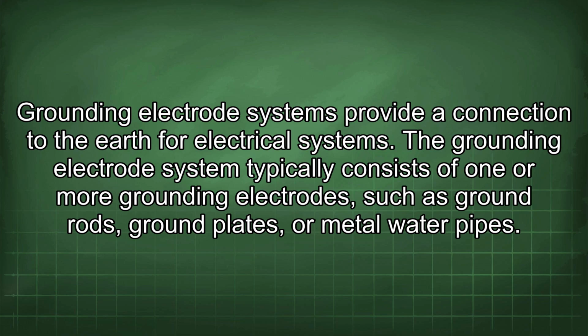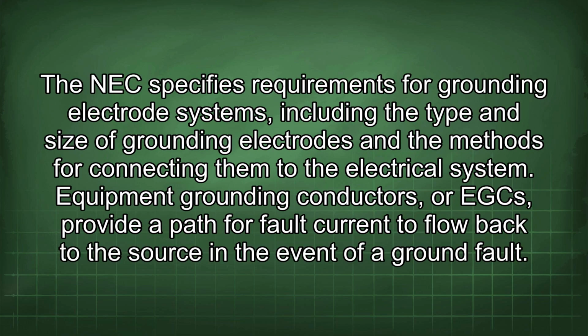Grounding electrode systems provide a connection to the earth for electrical systems. The grounding electrode system typically consists of one or more grounding electrodes, such as ground rods, ground plates, or metal water pipes. The NEC specifies requirements for grounding electrode systems, including the type and size of grounding electrodes and the methods for connecting them to the electrical system.